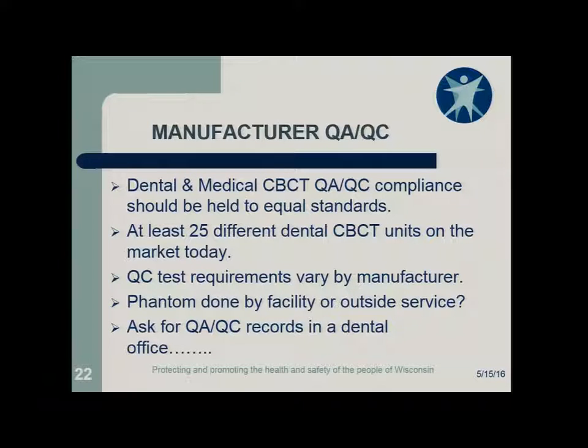I know. QC test requirements vary by manufacturer, phantoms done by facility or outside service. This is where in Wisconsin we've discovered a real sticky wicket. I have been told that cone beam CT falls under CT and its guidelines for providing a phantom to the facility. In Wisconsin, I want to say 9 times out of 10, there's no phantom. They've been told that there's a place they can go that's going to come in and do all their testing for them once a year for a fee, so they don't need the phantom.